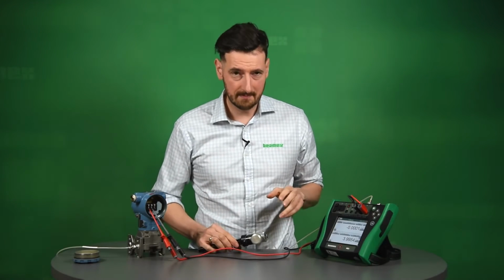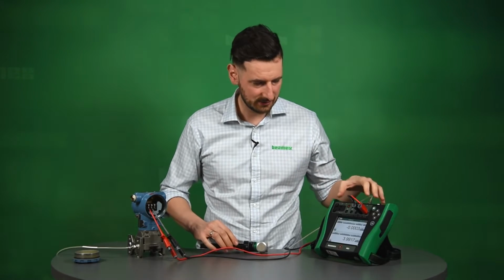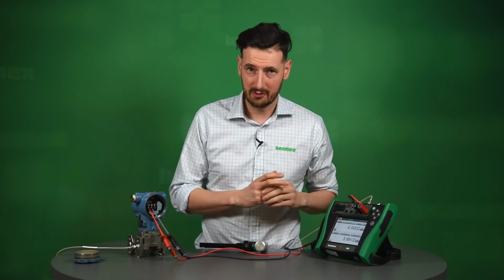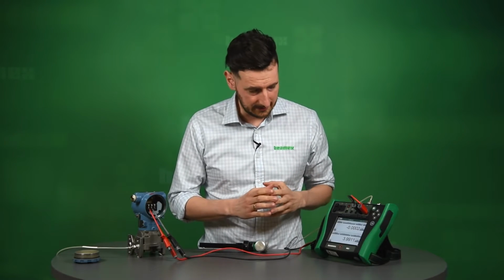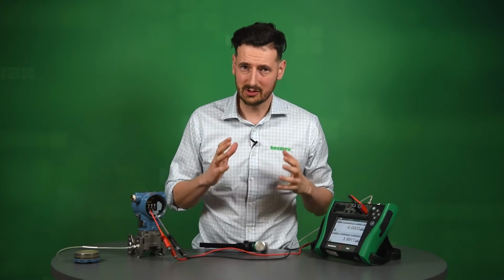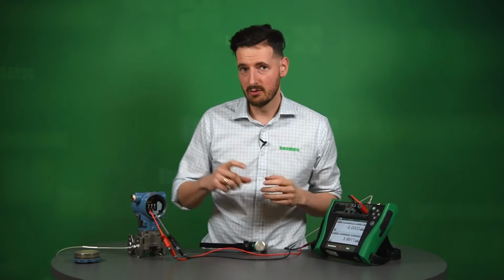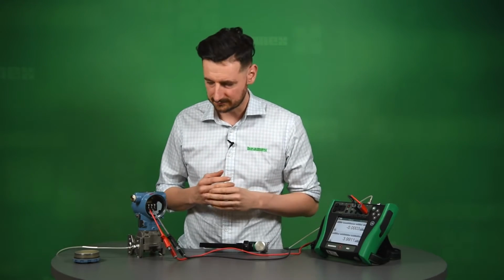I'm also going to be using the accurate calibrator. In this instance, I'm using a 30 psi module. The idea is that we aim to go 4 times more accurate than the unit under test. It's not always possible, and this is our aim. This is what we're trying to do.